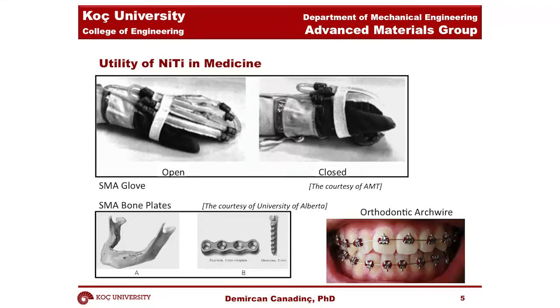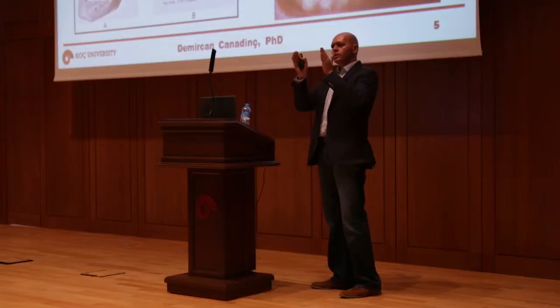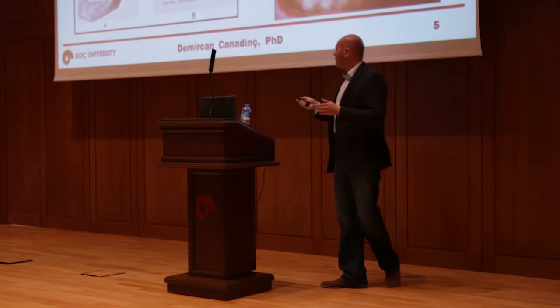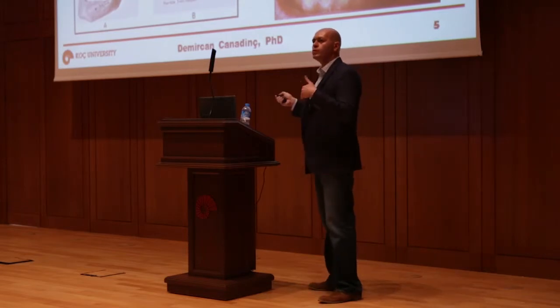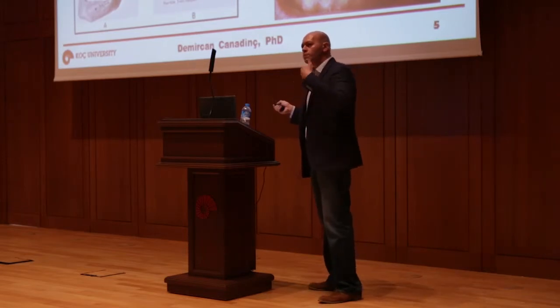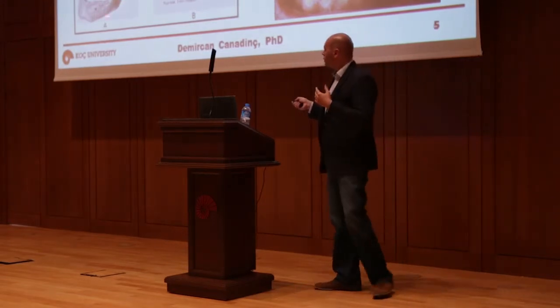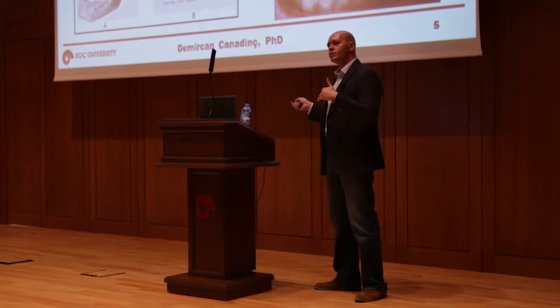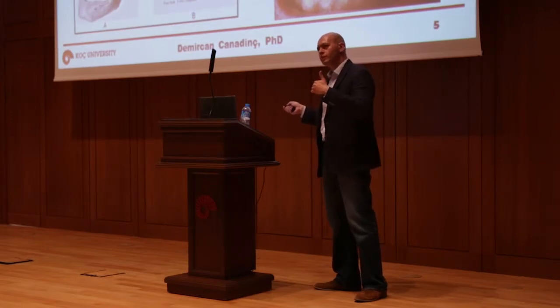And that tissue growth actually changes the shape of this staple, because it's like a regular paper staple, and the 2 ends are going to start moving apart from each other because there's tissue growing in between. And this is not what we want, because for optimum tissue growth, the load applied onto these 2 parts of the jaw has to be constant and at a certain level.